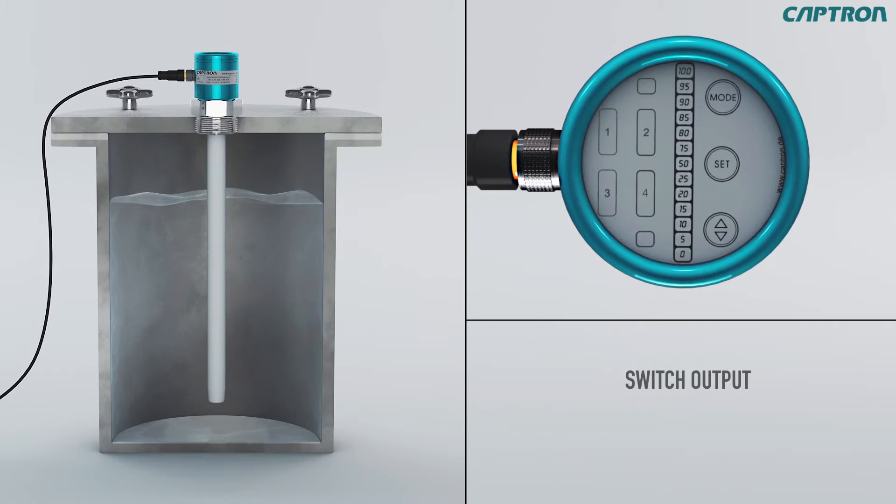Setting the switch output PNP1. The 0 and 100% displays will light up once again, as well as the NO or NC display for PNP1. NO stands for normally open and NC for normally closed contact. You can set NO or NC with the up-down button. Confirm your adjustment with set.